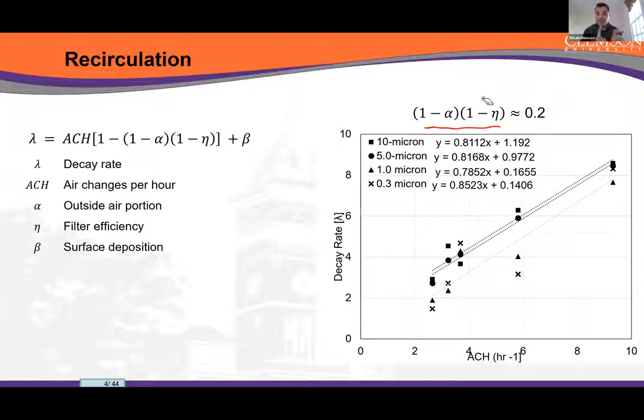Our case was right about here, with about 25% outside air in the cases I'm showing you, and about a MERV 8 filter, which is roughly 65 to 70% efficiency.